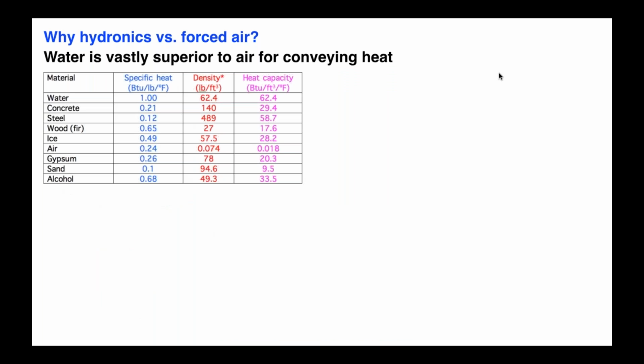So why is this the case? Well, I won't bore you with a lot of chemistry, so to speak, but I want you to look at an index called heat capacity. It's how many BTUs 1 cubic foot of a substance requires to take its temperature up 1 degree Fahrenheit. For water, a cubic foot needs 62.4 BTUs to raise its temperature by 1 degree Fahrenheit. Now, if we compare that to air, air only requires 18 thousandths of 1 BTU to raise a cubic foot 1 degree Fahrenheit.